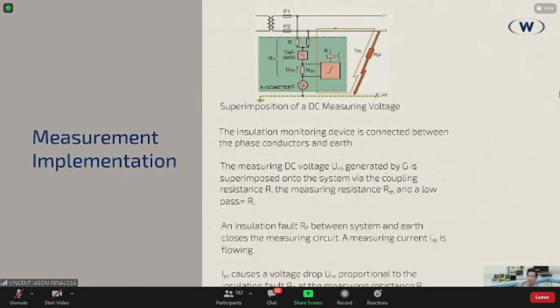Now, basically, what happens is that when an insulation fault between system and earth closes the measuring circuit, a measurement current IM is flowing, no? That IM is variable. You can set it from the device. It could be anywhere between 1 to 50 milliamps, depending on your protection goals. No? Now, that current causes a voltage drop proportional to the insulation fault at the measuring resistance. So again, it's still Ohm's law. No? And that's how we are able to measure insulation resistance online.